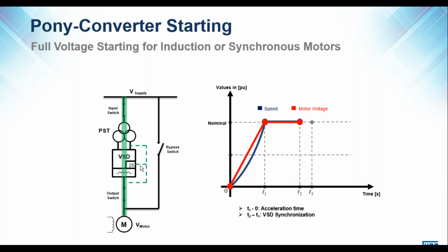we then apply the bypass. The VSD can be, or is, supplied with its own integral synchronous bypass relay. And so we have a period of synchronization that occurs. When we reach synchronization, we are able to close the bypass switch for a few milliseconds. Both the VSD and the supply are providing voltage to the motor, whereafter the VSD switch is opened and only the power from the supply is connected to the machine. It would be at this point that the full load can now be applied to the motor, whether through valves or vanes or other method.